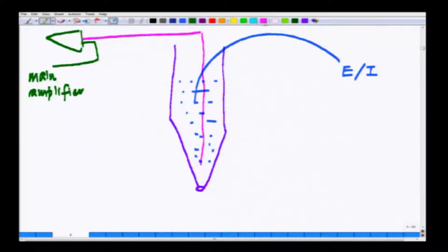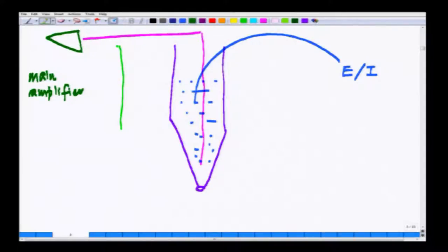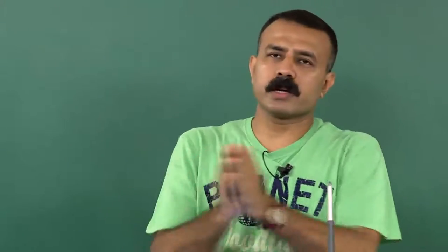Inside the patch electrode you put a silver electrode. The silver electrode is connected to something called a head stage amplifier, or the initial amplifier, and from here it goes to the main amplifier. Here you have the main amplifier and the ground electrode. The way it works: there are two amplifiers - one is the small head stage amplifier which picks up all the signals, then it transmits the signal to the main amplifier. In the main amplifier, all these analog signals are being processed.